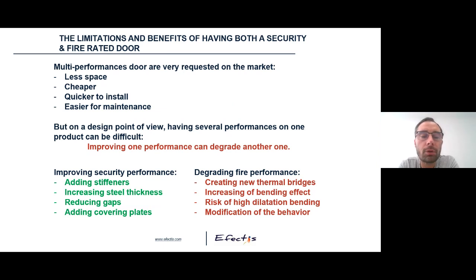But from a design point of view, having several performances on just one product can be difficult because when you improve one performance, you can degrade another one. For example, regarding the security performance, there are many ways to improve it. You can add some stiffeners in the leaf, but in this case, you create new thermal bridges between the hot face and the cold face. You can increase the steel thickness, but in this case, you increase the quantity of steel that will heat, and so you increase the bending effect. You can also reduce gaps, but you have risk of high dilatation, or add covering plates, but it will modify the fire behavior of the door. So improving a performance can degrade another one, and Peter will speak about how they manage these issues.